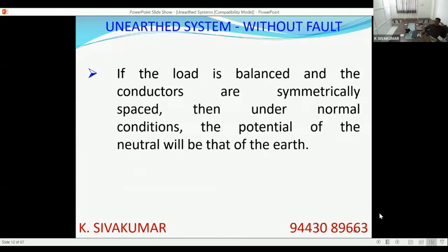We say that the neutral and the earth are at the same potential. Earth potential is always assumed to be zero. In this condition, balanced load and symmetrical spacing, the neutral potential is also zero. So we say that the neutral and the earth are equipotential points. The voltage of each phase with respect to earth will be equal to the voltage between phase and neutral. That is called the phase voltage.